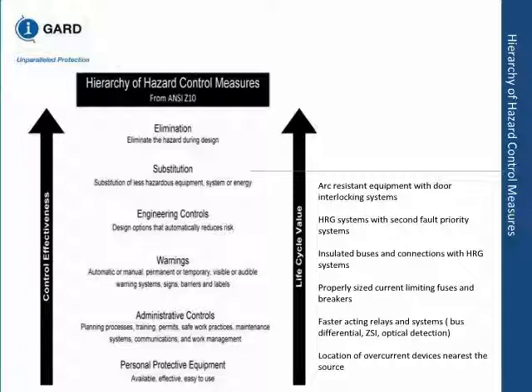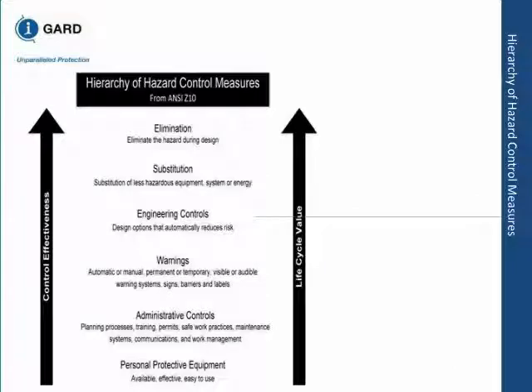Then look at some of the engineering controls. You can have maintenance switches, HRG system, interlocking, to assure. Now maintenance switches, you do realize it doesn't comply totally under engineering control because it has to take some human interaction. Anytime a human interaction is taken, probability of not following it is 1 in 10 in industry.